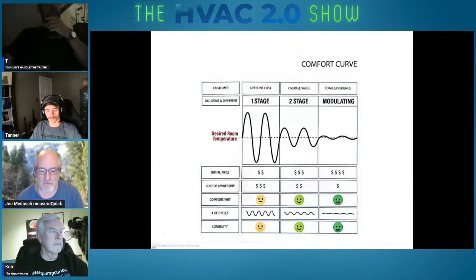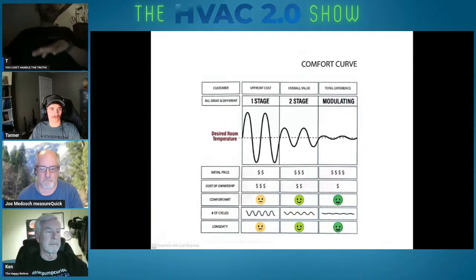Would you agree another part of the problem is they're getting temperature imbalances because the equipment's oversized? I wouldn't—let's put that off the table. No, let's keep that on the table, because our experience is people, no matter what they sell, are grossly oversizing the equipment. And if they grossly oversize it, two-stage isn't going to fix that.